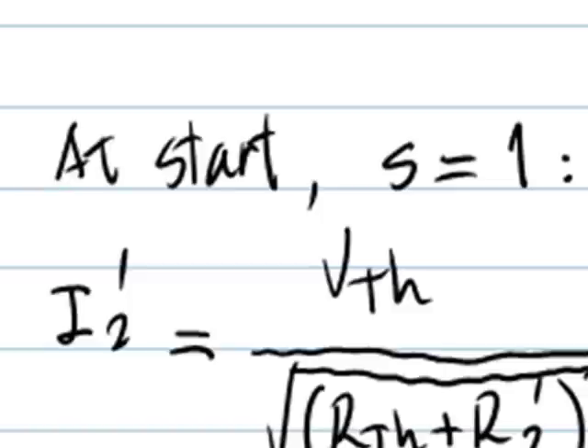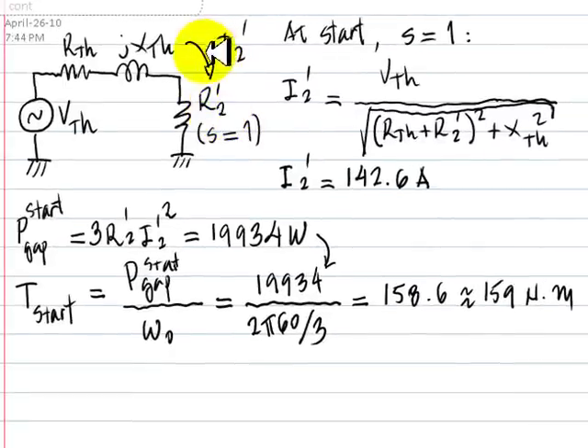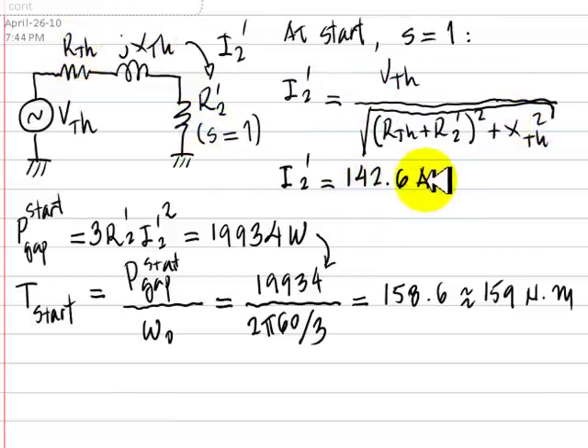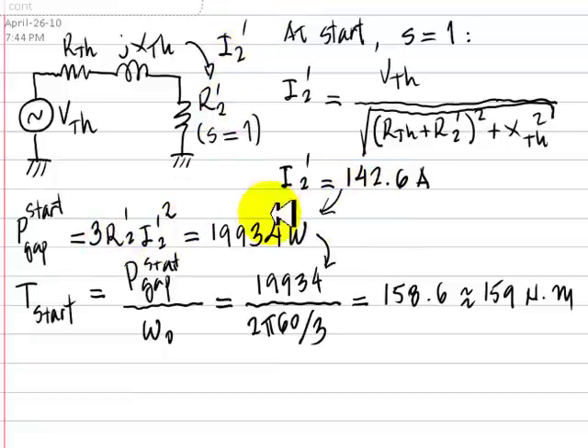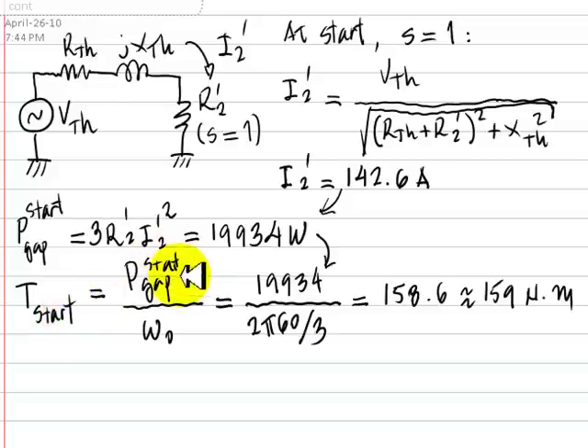For part B, we compute the starting torque. At starting, the slip is 1, and the equivalent circuit seen by the gap power resistor is just R2'. We compute the current as VTh divided by that impedance and determine the absolute value to be 143 amps. With that, we compute the gap power: 3 times R2' times I2' squared. We compute the gap power at the starting point to be roughly 20 kW. Dividing by omega naught, the starting torque is 159 Nm.